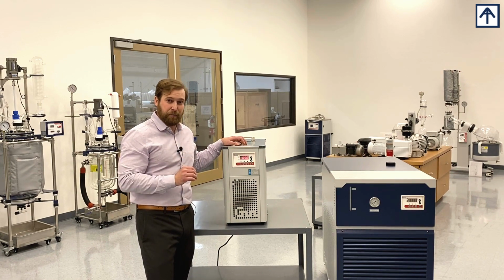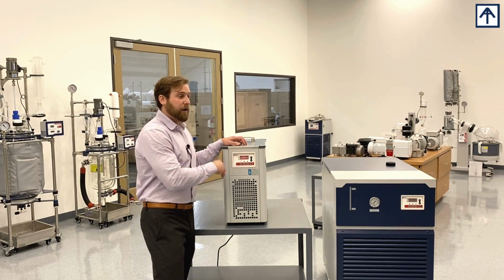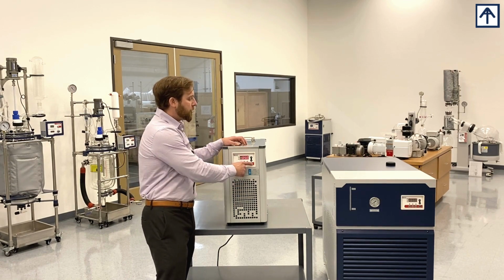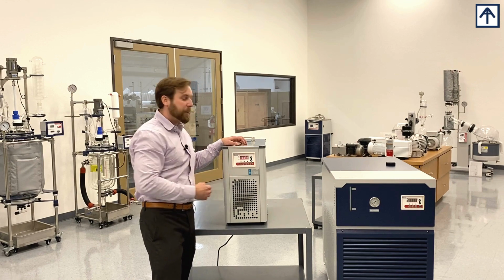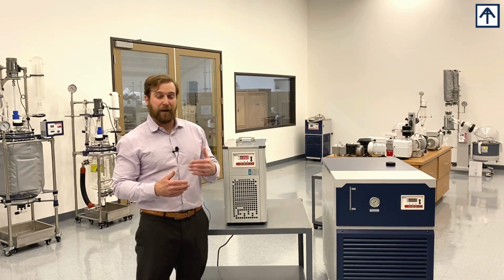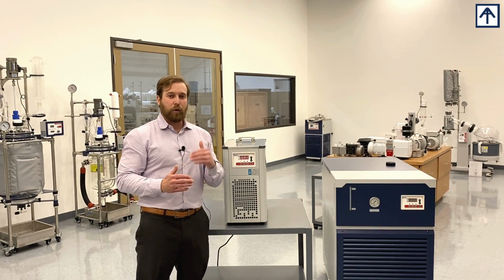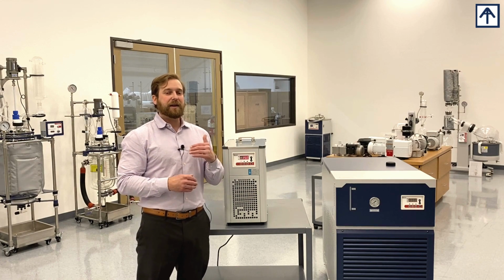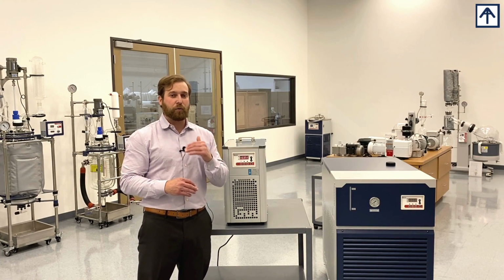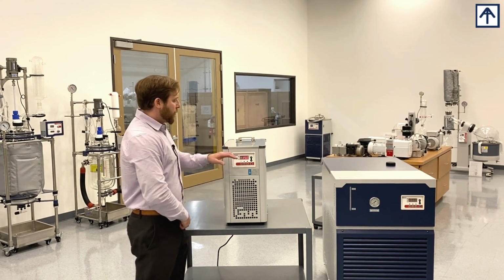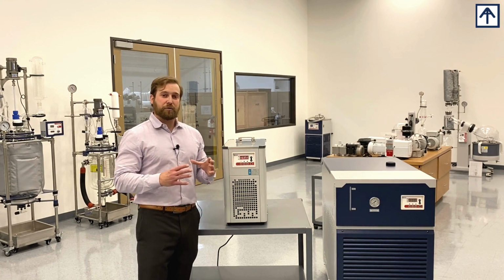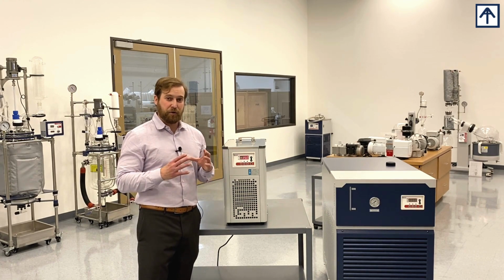The next step is the most crucial. After adjusting the upper temperature limit, we press set one more time, bringing us to the LF screen. The lower limit, or LF, is what controls the cooling of the unit. So when we're in the LF screen, this is our true set point - this is what the unit is going to cool to.